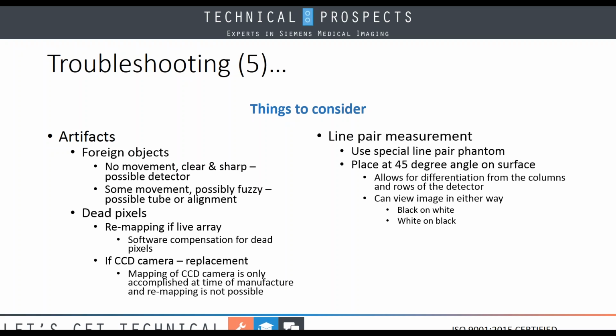Another thing for our viewing is line pair measurements. All right, here you're going to use a special line pair phantom. A little suggestion, especially here in our digital world today, so that we can differentiate on the lines that we're trying to see, is to place them at a 45-degree angle. When we look at our digital detectors, we have columns and rows. By angling the line pair phantom at a 45-degree, you can clearly determine, is that a line from your line pair phantom. Now, I don't care if you view it black on white or white on black, whichever is easiest for your eyes. Our goal is to get the highest lines per millimeter possible.